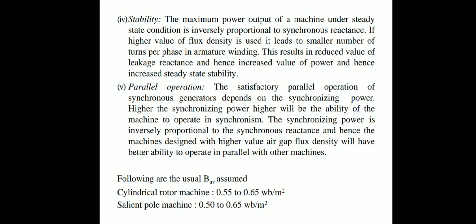The next one is parallel operation. The satisfactory parallel operation of synchronous generators depends on the synchronizing power. Higher the synchronizing power, higher will be the ability of the machine to operate in synchronism. The synchronizing power is inversely proportional to the synchronous reactance, and hence the machines designed with higher value of air gap flux density will have better ability to operate in parallel with other machines.